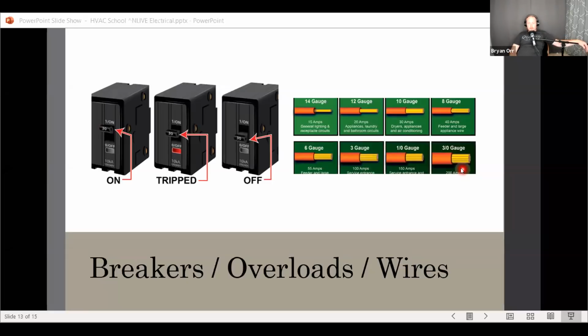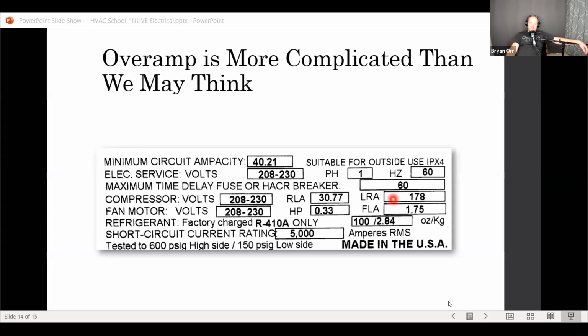This isn't aluminum. So there's a lot of different variables that factor in here. And there's also some derating variables, meaning there's some cases where if you're running through very hot areas, then you have to derate for that. Lots of different factors. But the one thing that's sort of a saving grace for us in our industry is that the manufacturers give us on the data plate what we size the breaker to and what we size the wire to, believe it or not. And if you follow that as an air conditioning contractor, you're safe. You've followed proper practices. And so let's use an example here.